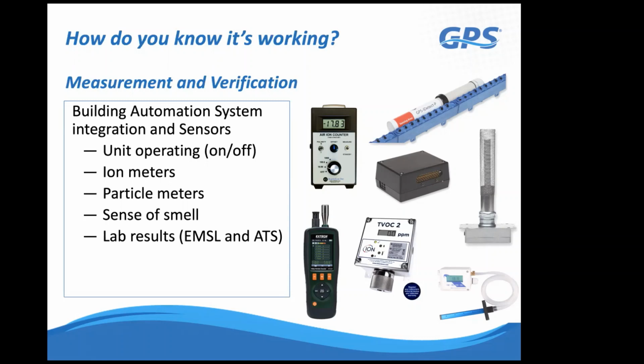It's not just telling you power's been applied like some of our competitors, who use a relay whose primary relay coil is attached to the primary power. We're actually sensing what's going on inside the circuitry and then telling the relay to close with our alarm contact. So that's actually a good way to know that it's on and operating properly with no faults.